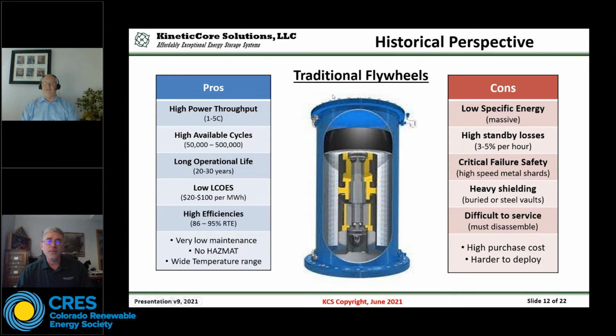When you do have to service a traditional flywheel, it actually requires you to essentially disassemble the entire unit to get at the motor generator, which is tucked in along the shaft of this particular example. So it's a bit of a challenge to get at some of the parts you have to work with. And we've already talked about the high purchase cost being a detriment, as well as a 10,000-pound flywheel being a bit harder to deploy than a battery you could potentially carry by hand and stack up somewhere.